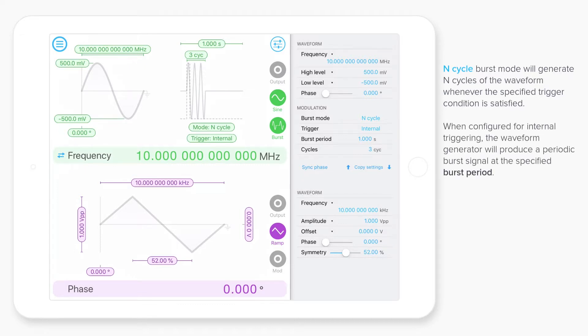So what we can do here is specify the burst period based on internal triggering mode. But another thing that we can do is specify a different type of trigger. So for example, we could use the external trigger. And so when that trigger event occurs, it will, in this case, produce three cycles of the waveform before settling and waiting for another trigger event.